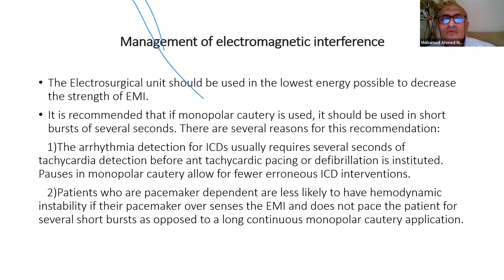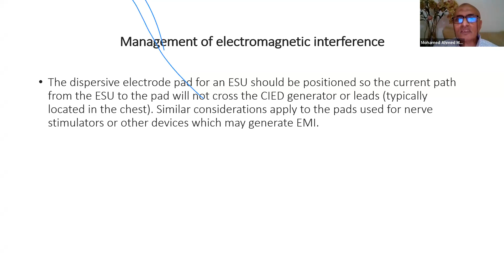Also, the dispersive electrode. The dispersive electrode, which is the earthing pad of the diathermy, we have to attach it to the lower half of the body of the patient. So the electric current will pass from the site of the diathermy to this dispersive electrode in the lower half of the body, and the pathway is away from the cardiac device. So the current will not produce damage or will not affect the cardiac device.